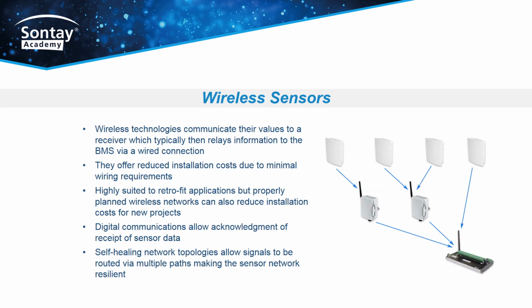Wireless sensors. Wireless technologies communicate their values to a receiver, which typically then relays information to the BMS via a wired connection. They offer reduced installation costs due to minimal wiring requirements. Highly suited to retrofit applications, but properly planned wireless networks can also reduce installation costs for new projects. Digital communications allow acknowledgement of receipt of sensor data. Self-healing network topologies allow signals to be routed via multiple paths, making the sensor network resilient.